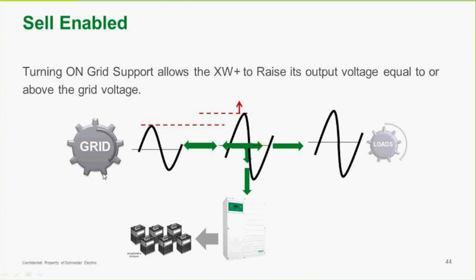So turning on grid support allows the XW to raise its output voltage equal to or above the grid voltage. So we're talking about AC here. If the battery voltage is above the grid support voltage setting, it will supply AC power that can be sold if Sell is also enabled. So there's actually two settings, grid support and Sell.